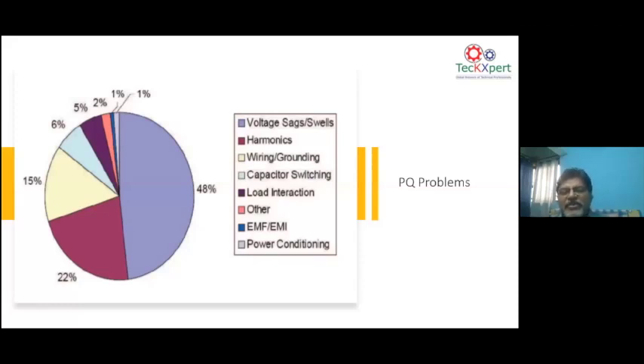So that means on the grid operation side, when you are handling capacitor switching, or when you have load throw-off, or some new loads coming, or switching of loads, or when there is a lightning strike, all this can create these sags and swells or transients. Harmonics, as I just said before. Then the other power quality problem, which many times we blame on harmonics, can be to do with poor wiring and grounding. This is very common. Many electronic cards, when they fail, some of the manufacturing companies, if you contact them, will say it's all harmonics. But the problem could be something to do with the wiring, because many times when you have a voltage sag or a swell or harmonics in the network, if the grounding is not proper, these problems can get amplified.